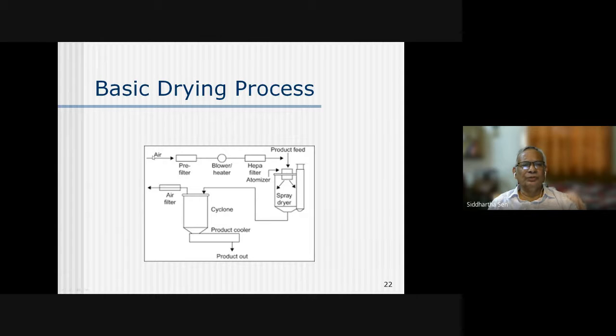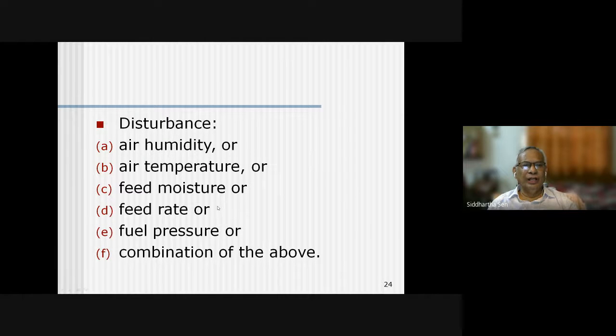Suppose I want to control only the temperature of the air. What are the disturbances which could affect the moisture content at the output? It could be the air humidity - initially the air may contain some moisture, or air temperature - the initial air may be hot or cold, or the feed moisture, or the feed rate, or in some cases the fuel pressure where we use fuels, or a combination of these.